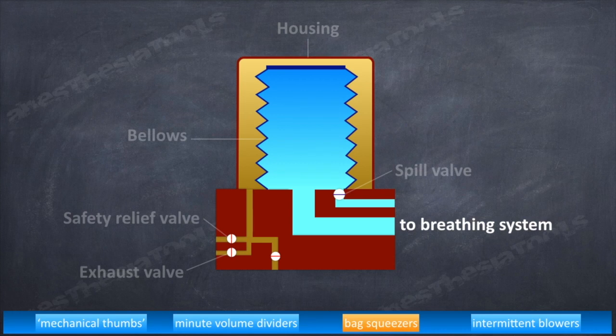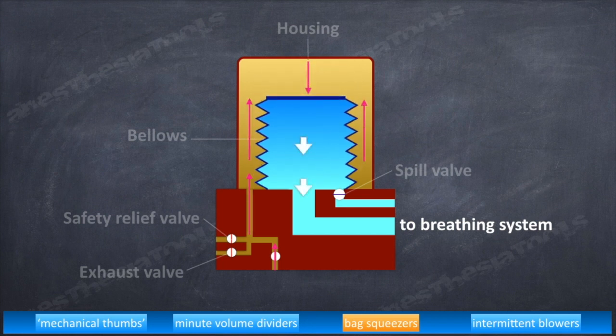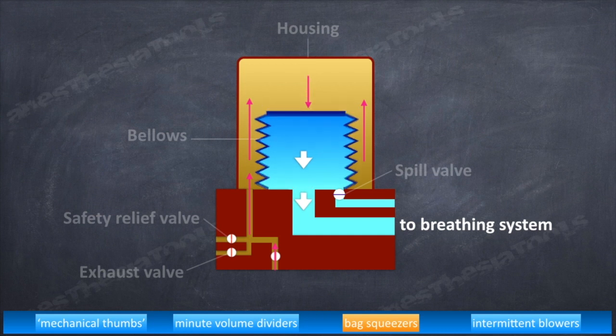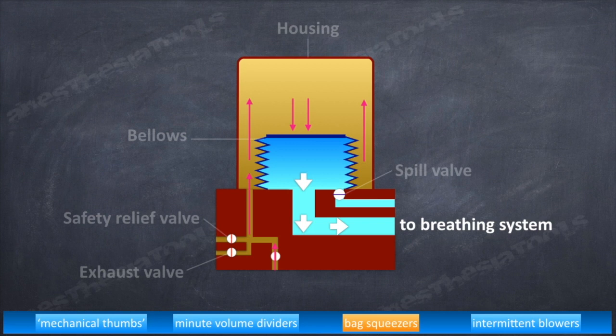First, the drive gas flows into the housing. Then it starts to push the bellows from outside. Once the bellows are pushed down, the fresh gas or patient gas within the bellows gets pushed into the breathing circuit. As more drive gas gets in, bellows get pushed more and more. Flow occurs into the breathing circuit.